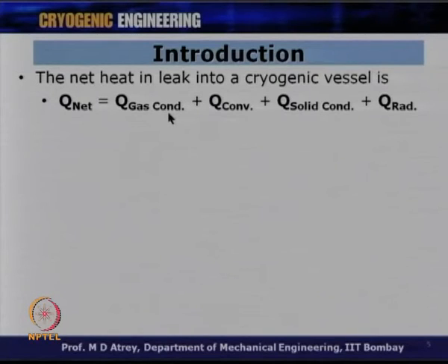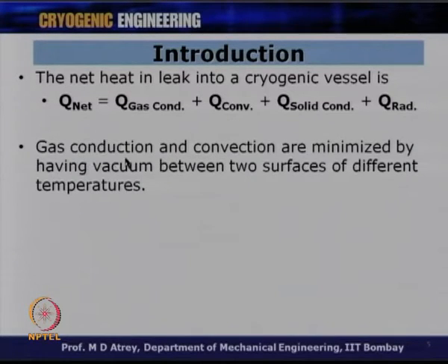It will not be equal to 0, but we can say that the amount of gas available in a particular space would be negligible, so we can neglect Q gas conduction, and therefore, we can also neglect Q convection, which is caused by the presence of gas in that particular space. So, if I get a good vacuum, Q gas conduction and Q convection can be completely taken care of, or they will get minimized. The heat inlet occurring because of gas convection and conduction is minimized by having vacuum between two surfaces of different temperatures.